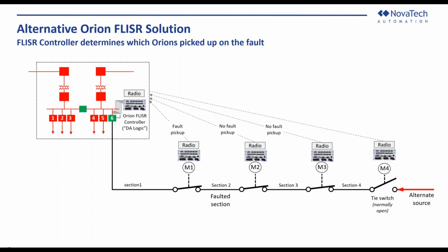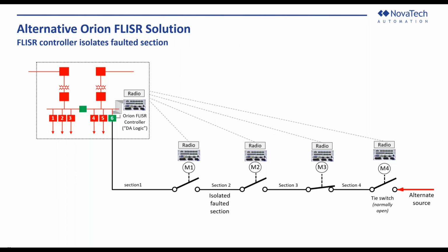The FLISR controller will then determine which line picked up the fault. As you can see, M1 is reporting a fault pickup, and M2 and M3 have no fault pickup. So now we want to isolate the faulted section from the unfaulted section, right? In that case, the FLISR controller isolates the faulted section by opening M1 and M2, and then it calculates the pre-fault demand amps from the unfaulted section to see if the load can be picked up from an alternate source.